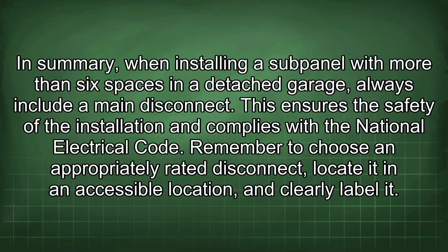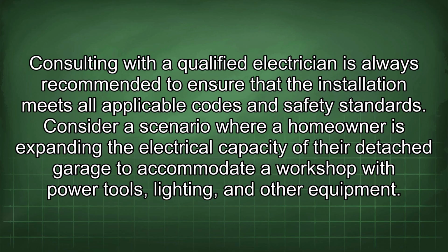In summary, when installing a subpanel with more than 6 spaces in a detached garage, always include a main disconnect. This ensures the safety of the installation and complies with the National Electrical Code. Remember to choose an appropriately rated disconnect, locate it in an accessible location, and clearly label it. Consulting with a qualified electrician is always recommended to ensure that the installation meets all applicable codes and safety standards.